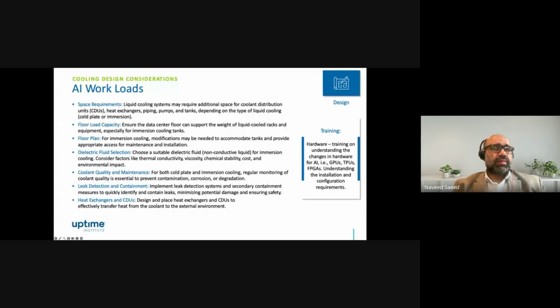And just an example, if you are operating a data center that has an average rack density of 20 kilowatts per rack air-cooled, which is traditionally the higher end of the density for a traditional air-cooled system, and now you're going to put 100 kilowatts per rack there, that means you need a quarter of the space of your white space. The rest of the space is not required because you will be running out of power and cooling in that facility. And what you do with that space is something you have to think about. And if you're designing a new greenfield data center, the split of gray space to white space is going to change significantly depending on your rack densities. There will be a much lesser requirement of white space and much more requirement for gray space to fit out all the upstream infrastructure, including CDUs, chillers, pumps, UPSs, power distributions, generators, and all those sorts of things.